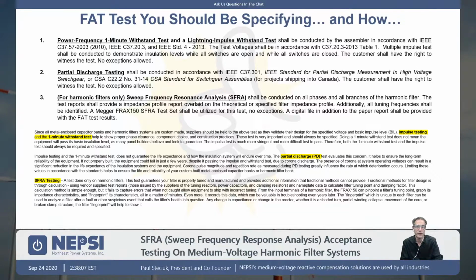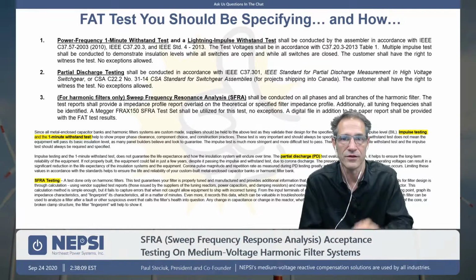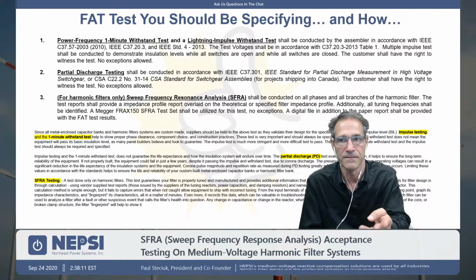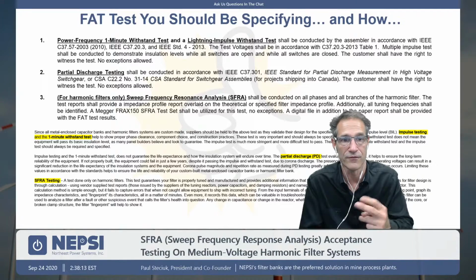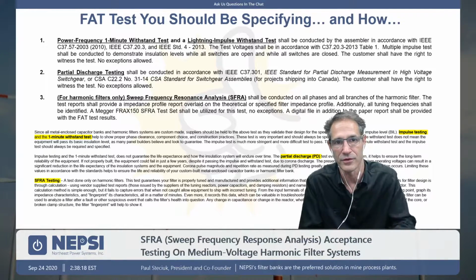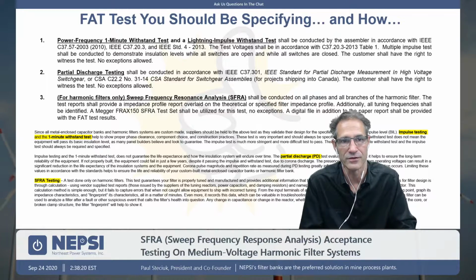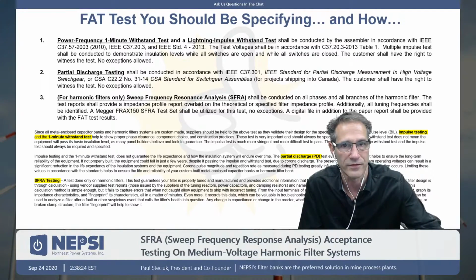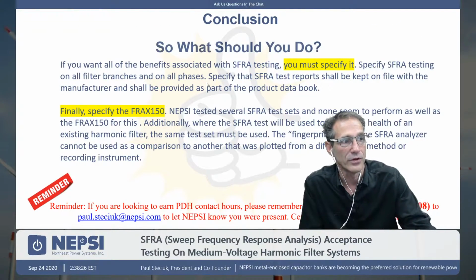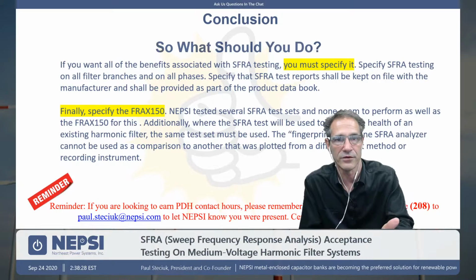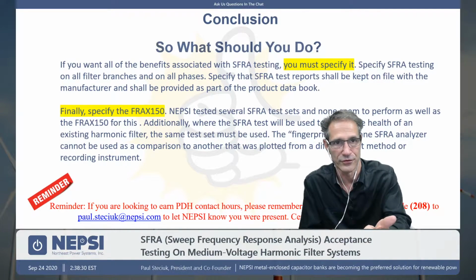So what I did is I put on this presentation the 3 ways to specify these tests. The first 2 apply to capacitor banks. All 3 apply to harmonic filters. So specify those. It's a way to guarantee that you're going to get equipment that will make it for its lifetime. So in conclusion today, if you want SFRA testing, for sure, specify it.